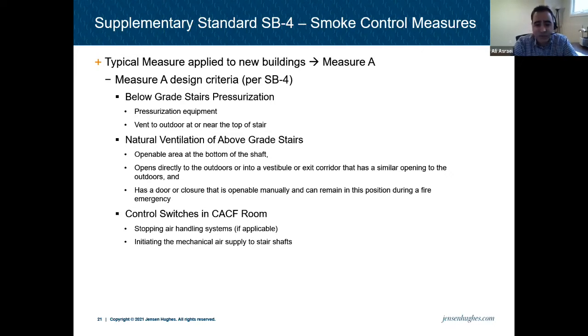For above grade stairs, it's only natural ventilation which is required. So technically the door at the bottom of the stair, if you can open it, and as long as it can stay open, and it can be manual. You see in a lot of buildings they have the automatic door opener with the fire alarm. It's not a requirement, because the code is asking that it's openable and can remain in this position during a fire emergency. So if they have a magnet, sometimes I've seen people putting one on a wall so you can push the door open and it stays in open position, or some sort of chain I've seen sometimes.